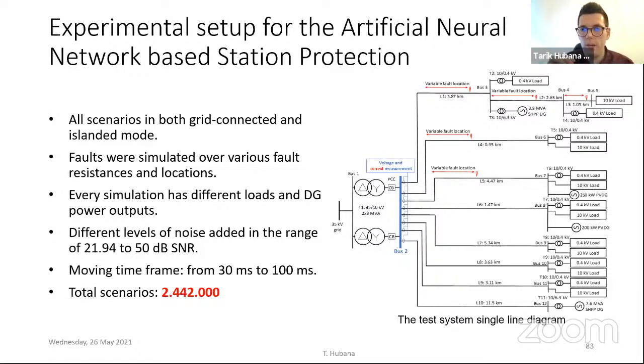So when each of these methodologies is used, it goes by the case. For example, the fault happens in the system. The number one algorithm detects the fault and classifies the fault type. The number two algorithm detects the faulty feeder. And now we have a number of algorithms for each of these feeders, which evaluate the fault location. So actually, yes, we do have a number of trained networks and a number of methodologies that are used depending on the fault case in the system.